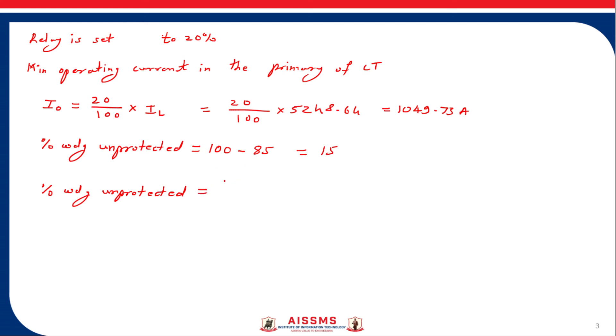So it equals resistance which is connected in neutral to ground, R into this minimum operating current which we calculated in previous step, divided by voltage. But here we must consider per phase voltage. So it equals R into 1049.73 divided by 11000 by root 3.